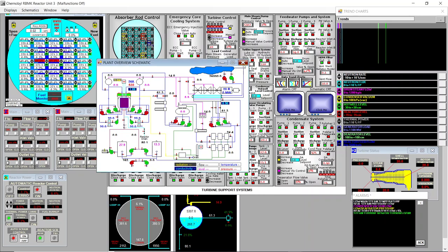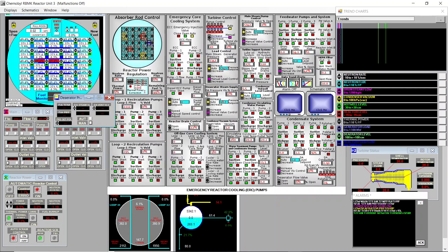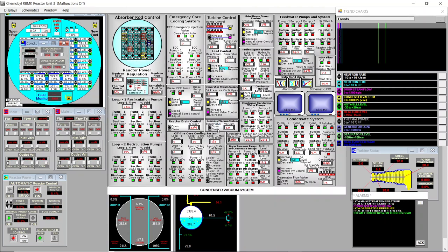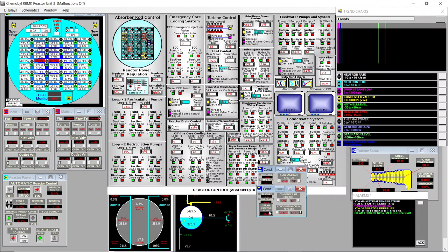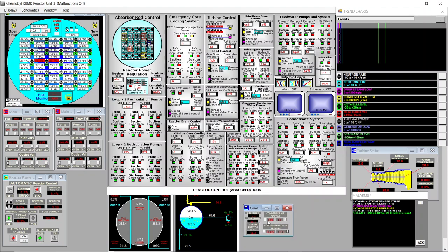The third reason is in the condenser vacuum system. There is here a switch, which now is on because I clicked this during the startup procedure. If you forget to click this and you reach I think 16 kilopascal or so, which is the ejection pressure of the vacuum, the vacuum will not build up, so you will be stuck at a very low vacuum.